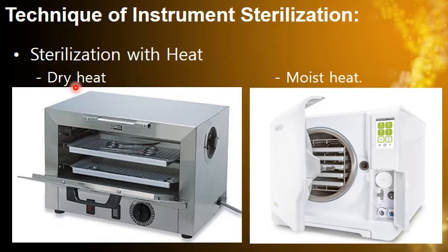And after the end of the sterilization cycle, I must leave it until it cools down. So we have warming up, the sterilization process, and the cool down. All these will take about 2 to 3 hours, which is a long time in your clinic, where your clinic time is about 3-4 hours, and you have only 1 set or 2 sets of instruments. This sterilization method will be useless for you.